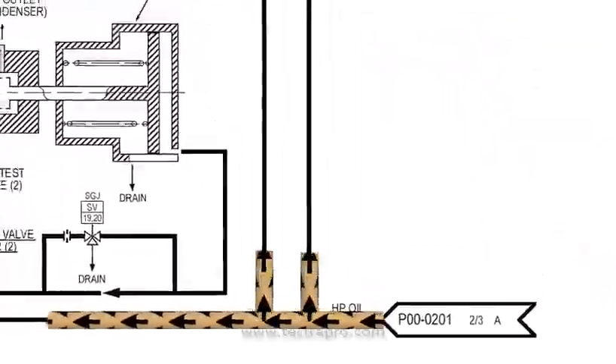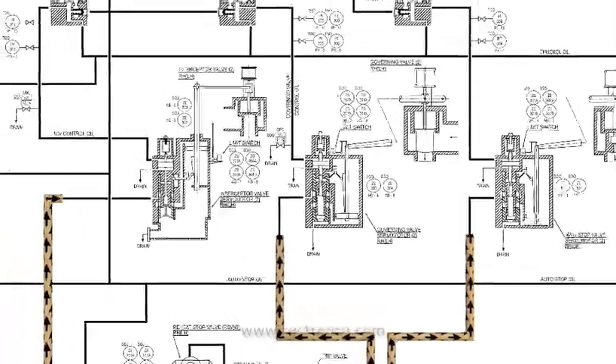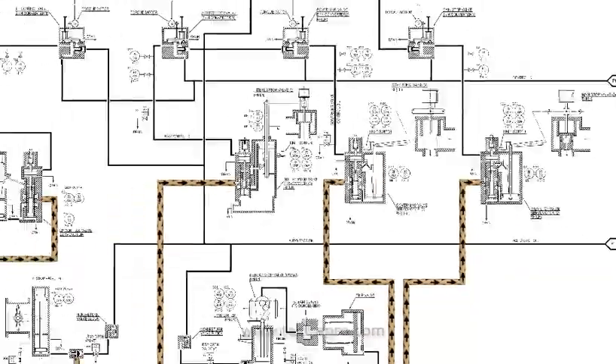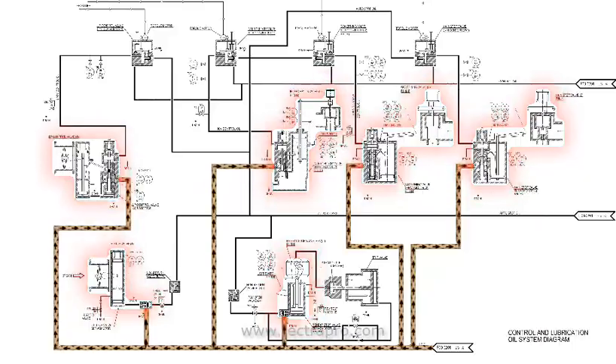The oil is divided into several different paths. High pressure oil goes to the electro-hydraulic converters, which in turn control the intercept valves, governing valves, and main stop valves.